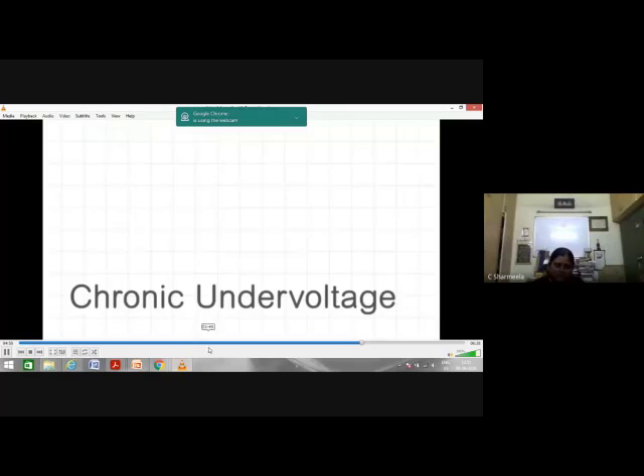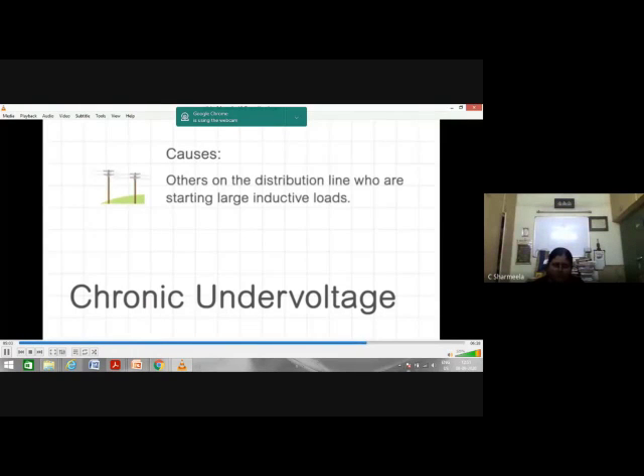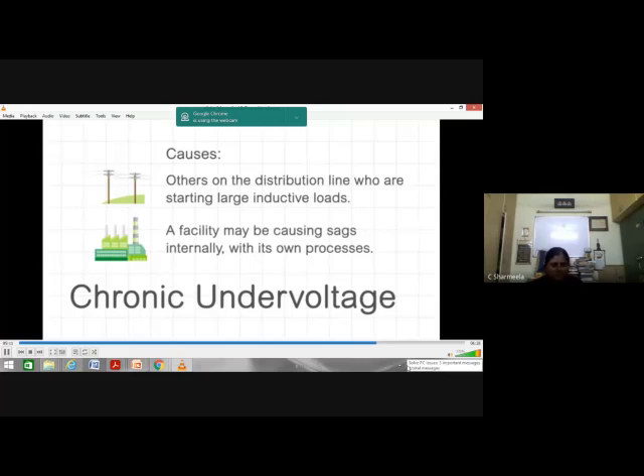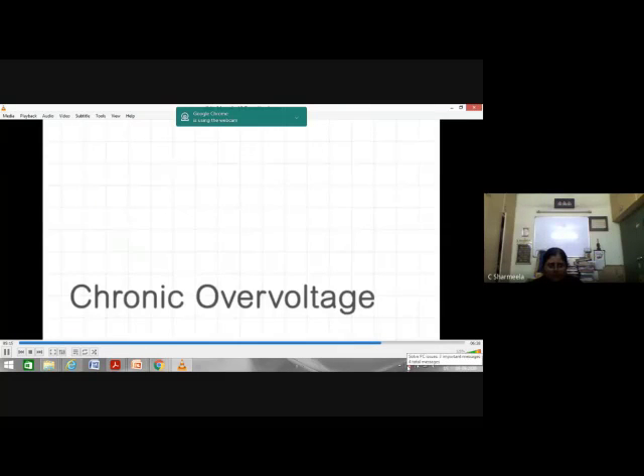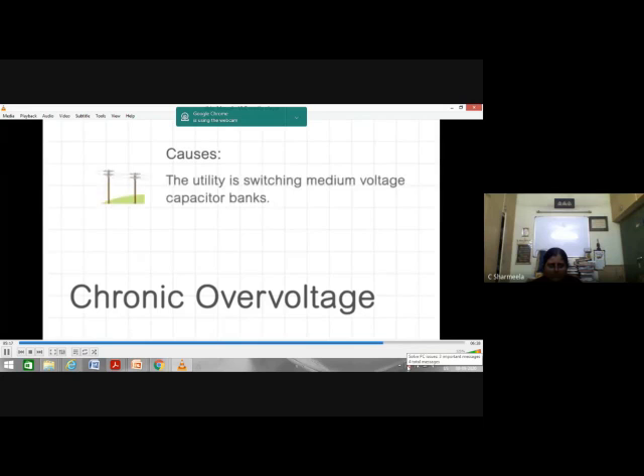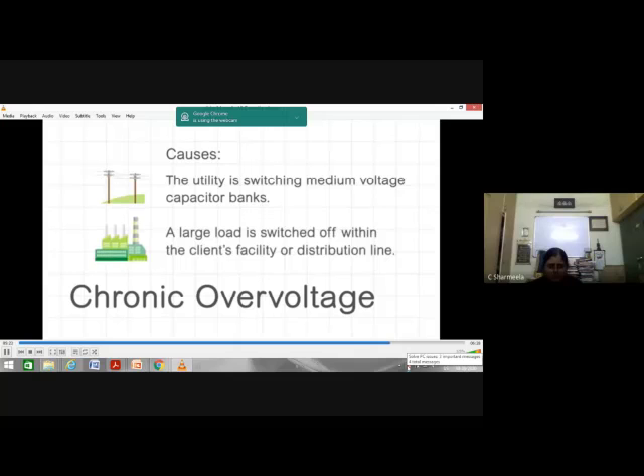Chronic undervoltage can happen because the consumer is at the end of a distribution line. The neighboring customer may be starting a large inductive load. The consumer may cause the sag with their own industrial process. Chronic overvoltage normally happens because the utility is switching capacitor banks on the medium voltage network. A large load is switched off within the client's facility or the medium voltage distribution line.